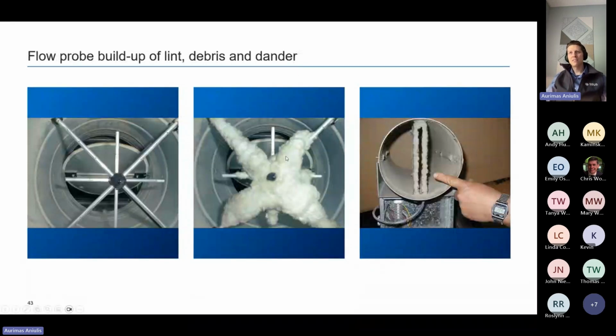As this flow probe starts to foul up, your CFM reading starts to drop. So the valve starts opening, thinking it needs more air, and eventually reaches a full open condition and a 0 CFM reading. And that's when the room goes into alarm and everybody starts freaking out, going, it's unsafe, we need to shut it down, call the experts. What do we need to do?